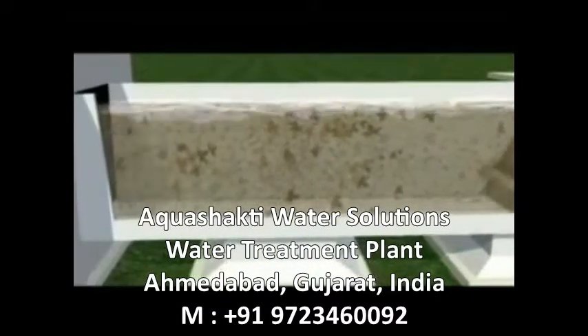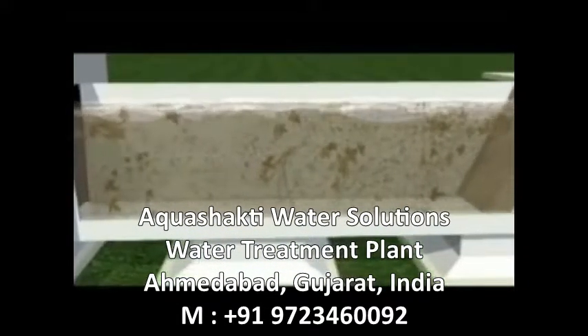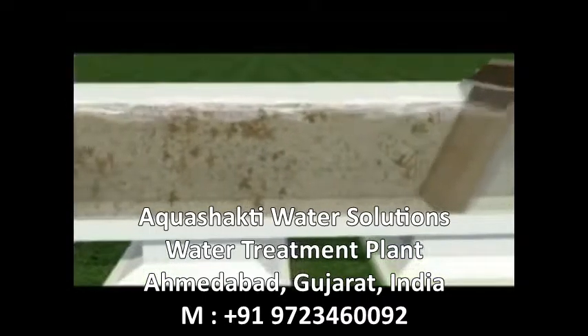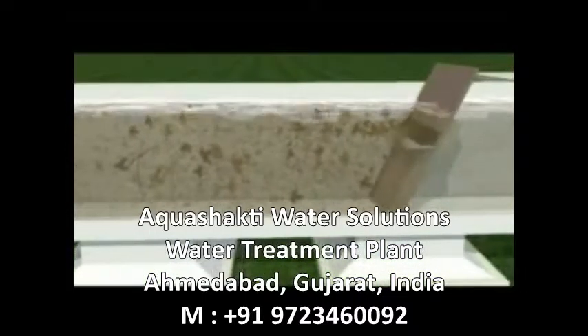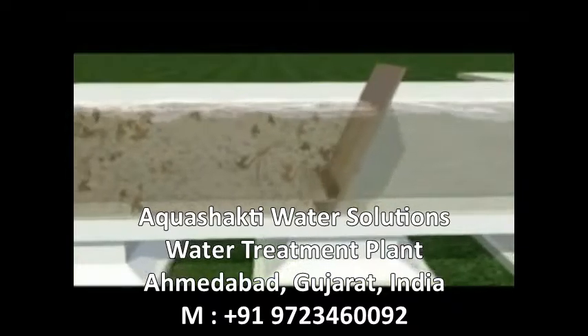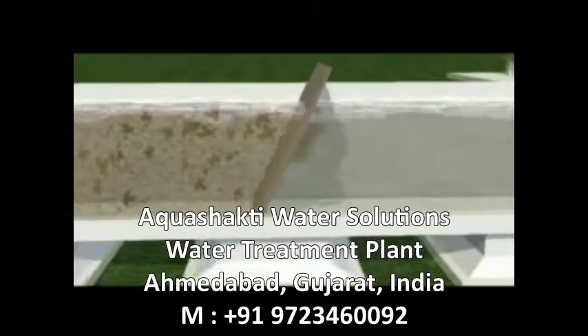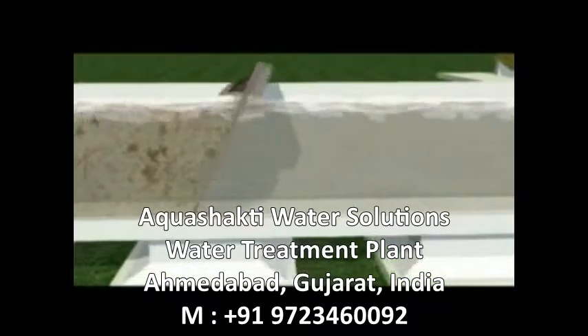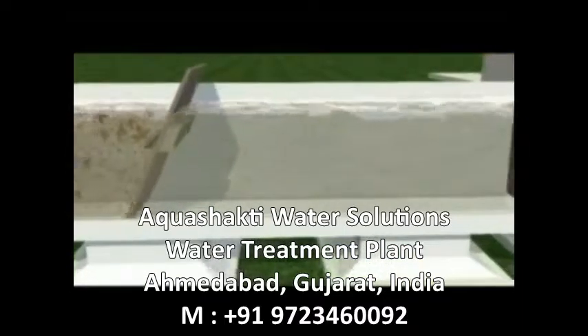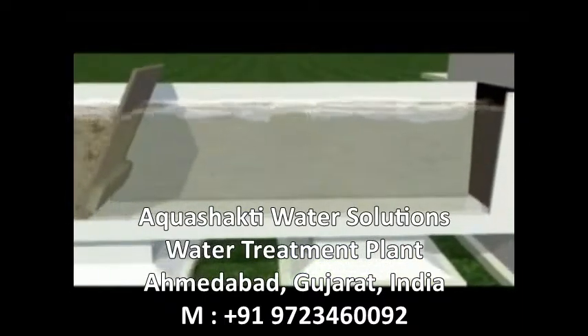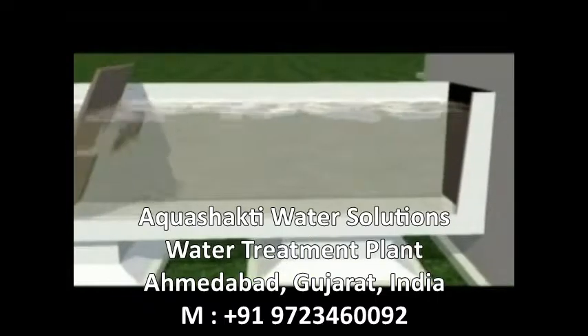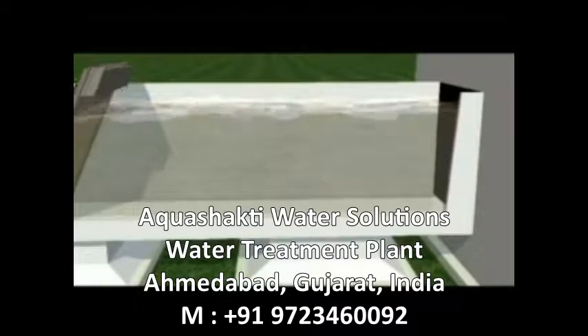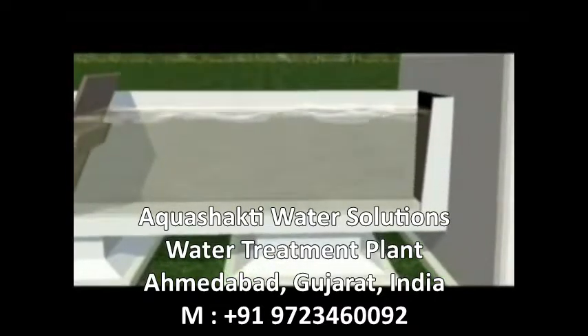By passing water through mesh screens, we remove sticks, water weeds and other large foreign objects. The air takes some odours and gas from the water and allows some dissolved metal salts to separate to be filtered out. We add air by cascading the water down a tower, spraying it into the air or bubbling air through it.